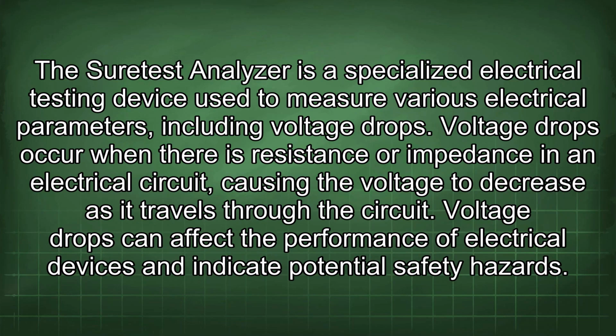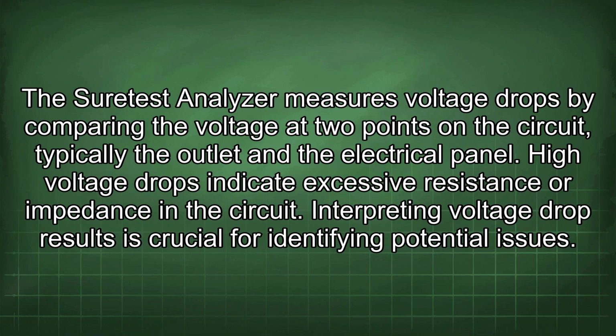The Suretest Analyzer is a specialized electrical testing device used to measure various electrical parameters, including voltage drops. Voltage drops occur when there is resistance or impedance in an electrical circuit, causing the voltage to decrease as it travels through the circuit. Voltage drops can affect the performance of electrical devices and indicate potential safety hazards. The Suretest Analyzer measures voltage drops by comparing the voltage at 2 points on the circuit, typically the outlet and the electrical panel. High voltage drops indicate excessive resistance or impedance in the circuit.